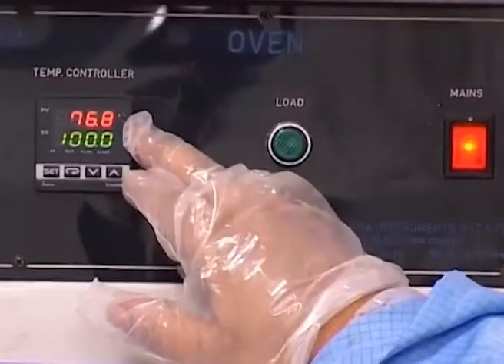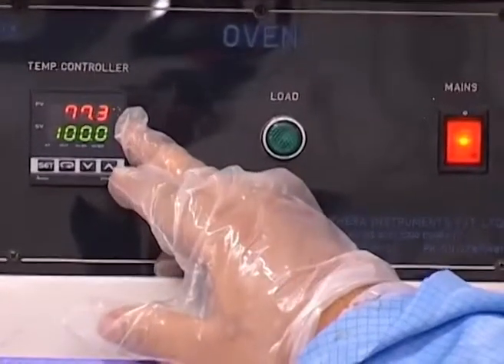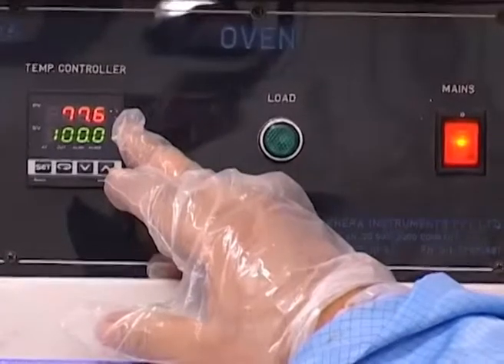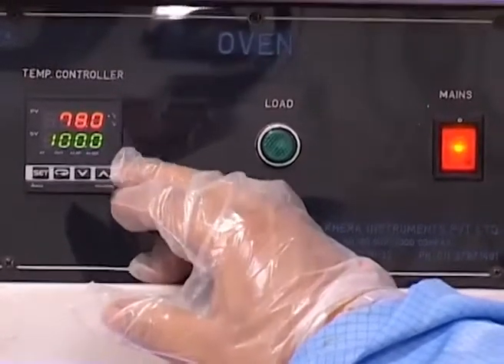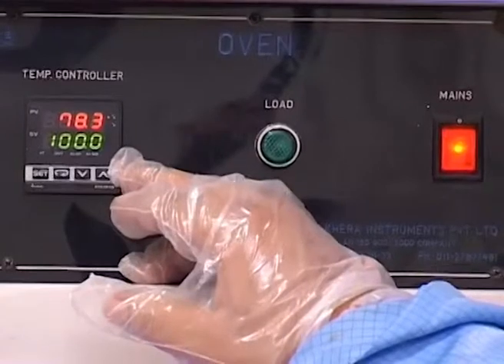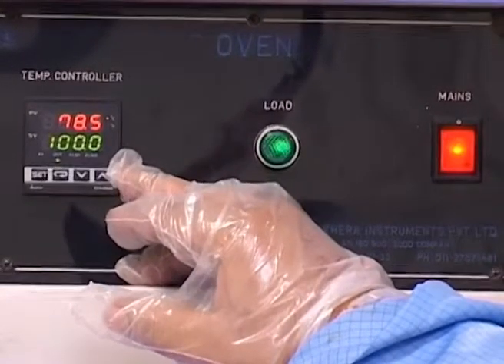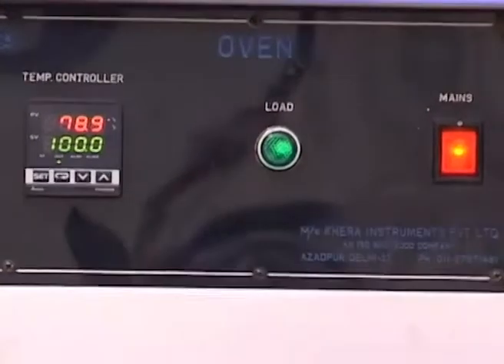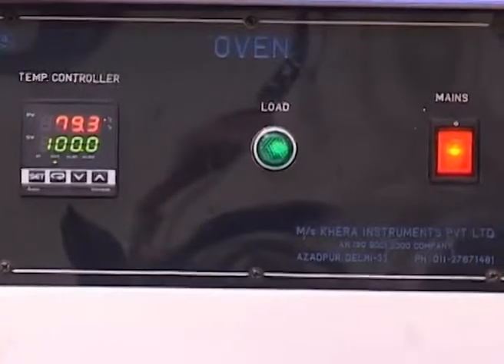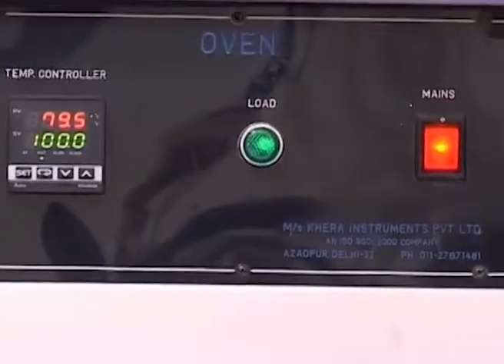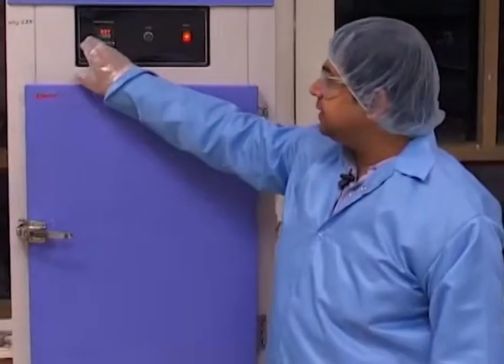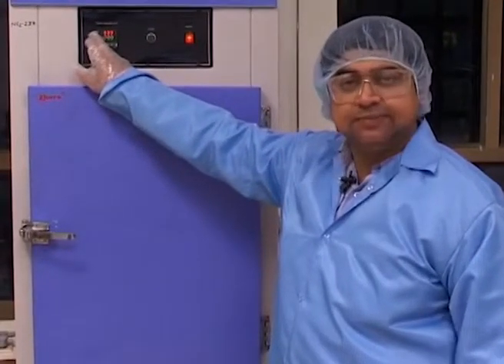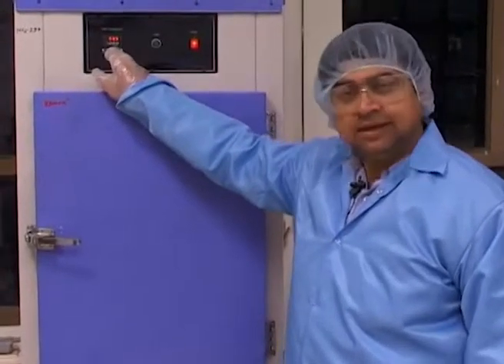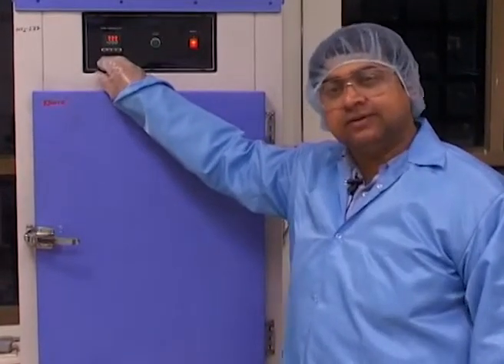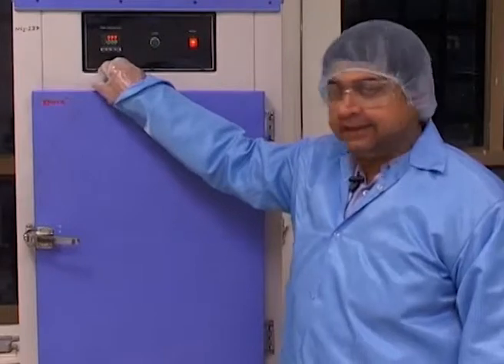So this temperature, which is also the proportional integral differential temperature, slowly equalizes with this set value after a while. There is some kind of flickering around the set value. It does that flickering and slowly attains the set value point. Now, as you are seeing here, the variable value has almost reached 100 degrees, and this is time enough for our wafer to get loaded inside and get dehydrated.